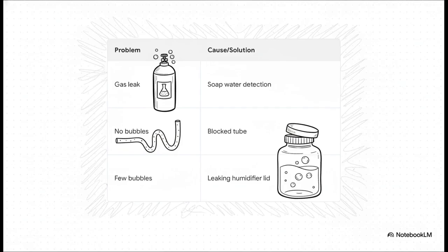When you're troubleshooting these devices, you gotta be quick and logical. Suspect a cylinder is leaking? Just apply a simple soap and water solution around the O-rings and Bodok washer. It will instantly reveal dangerous leaks by bubbling up, exactly like checking a bicycle tire for a puncture. For a concentrator, if the humidifier bottle has absolutely no bubbles, you immediately feel around for a kinked or blocked delivery tube. And if there are just a few weak bubbles, you check to make sure the humidifier lid is screwed on tight enough.